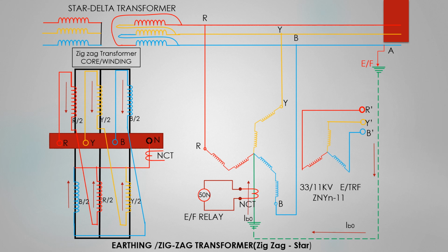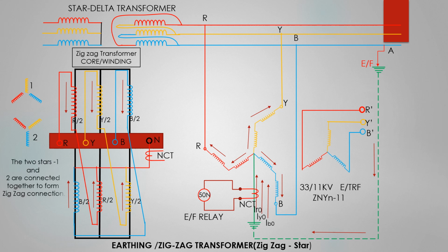Again, during an earth fault on the primary side, zero phase sequence current, ZPS, which has the same phase for the three currents, IR0, IY0, IB0, flows in the transformer winding through the earth connected neutral. The earth fault current gets a small impedance to flow within a short period of time.